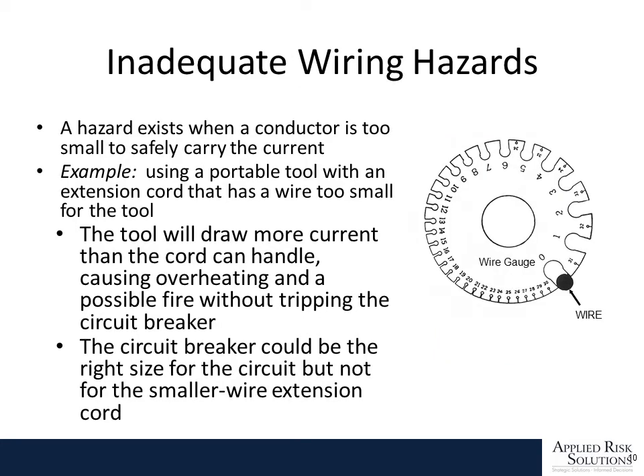Inadequate wiring is a serious problem. A hazard exists when the wire you're trying to use is too small for the amount of current. In a household wiring system, you have a breaker which is set up to carry so many amps, and the wires are designed to carry more amps than the breaker, so that if you plug in something, the circuit breaker will trip or the fuse will blow before the wire gets too hot to melt. This is what prevents us from burning homes down.